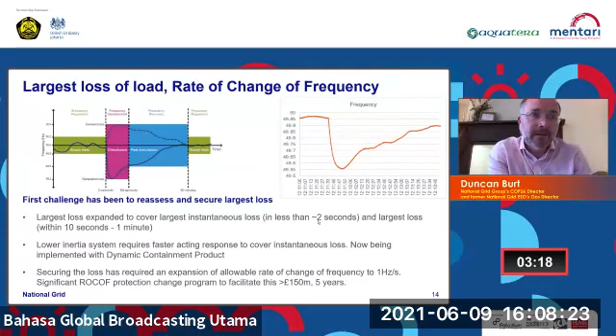Alongside that, we again are looking at the level of fault infeed from the system. Fault infeed is effectively the pulse or support that you get during a fault, which helps to stabilize the system. As we reduce the number of large generators on the system, the fault infeed declines, and therefore we have to contain that. The main issue we are seeing on the UK grid is effectively establishing minimum regional levels for the reliable commutation of current source HVDC interconnections.